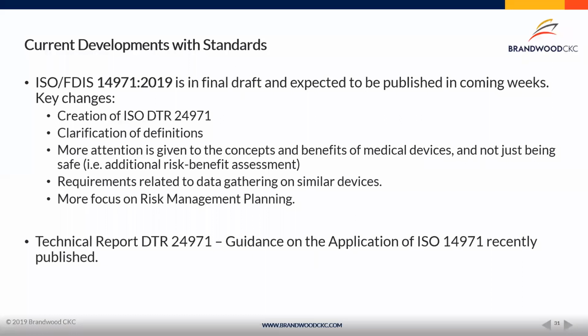You have to be able to say that we've looked at similar devices and here are their risks, or here are their risks and they match up with ours, but here are the probabilities and severities that they've come up with. So doing that as part of your database searches, doing that as part of your literature searches to really truly understand what other risks have you not thought about, but also what other risks could you further qualify based on information that's out there.